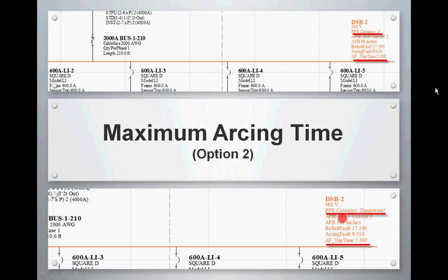And guess what? What was the maximum arcing time? The person had not changed the value that was put by default at that time, I don't know, it was 9,999 seconds. Can you imagine why everything was dangerous, okay?